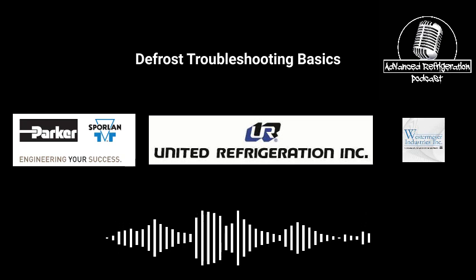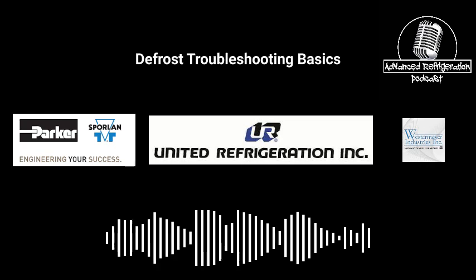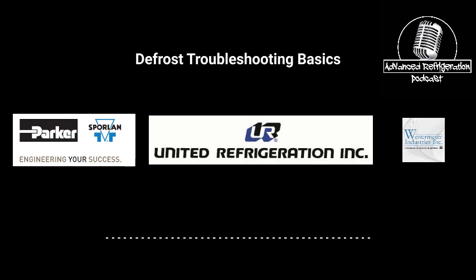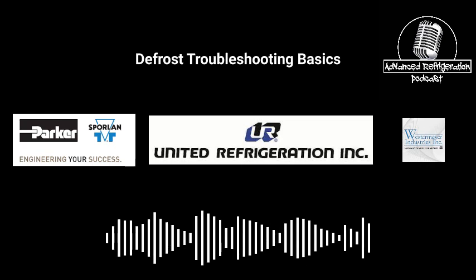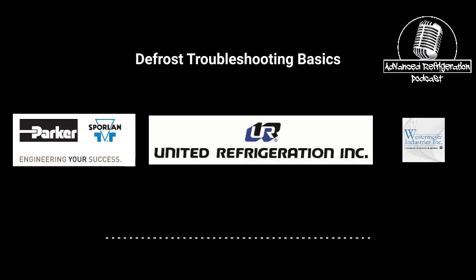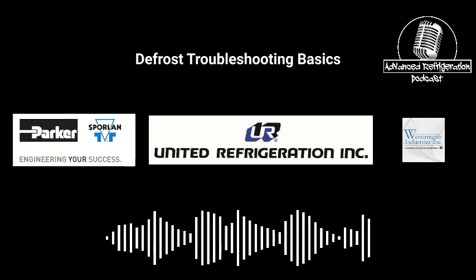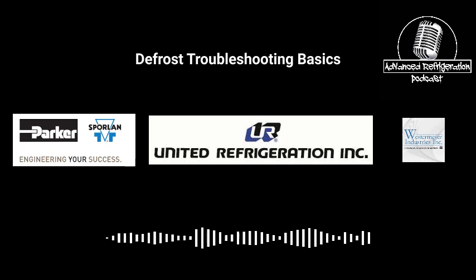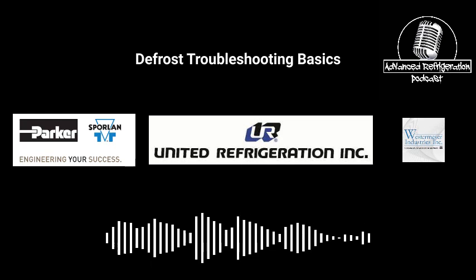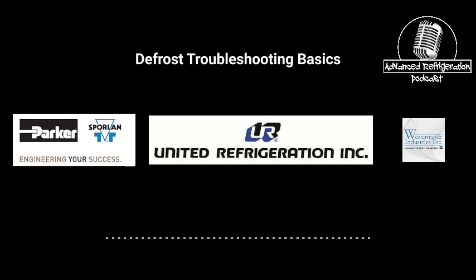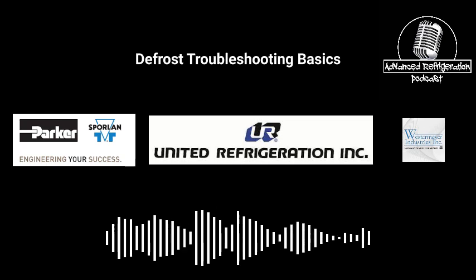But I will agree, without termination, it makes it extremely erratic, and not being able to float the head down makes it even more erratic. So, I'm not a big fan of OLDRs. I would much rather have a DDR valve. It's going to give you a much smoother, proper defrost, and you just eliminate the receiver hunting issues.